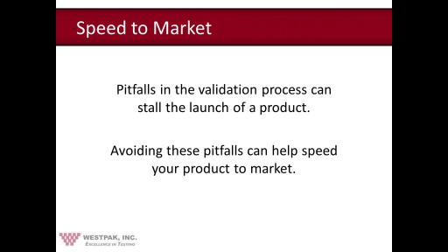So we've just discussed the various components that comprise a protocol written to satisfy the ISO 11607 guideline. Now let's discuss some elements that can help us get through the validation process with as few snags as possible. Seemingly minor details in your protocol have the ability to turn molehills into mountains, and we want to help you avoid that. Some of the most significant issues that we've seen here at Westpak can be lumped into one category of flexibility. As Kevin mentioned, stating your acceptance criteria and then meeting that criteria is the structure behind conducting a package validation test. However, there are situations where the inability to meet specific criteria doesn't necessarily jeopardize the validity of testing results. And we will go through a few of those examples now.